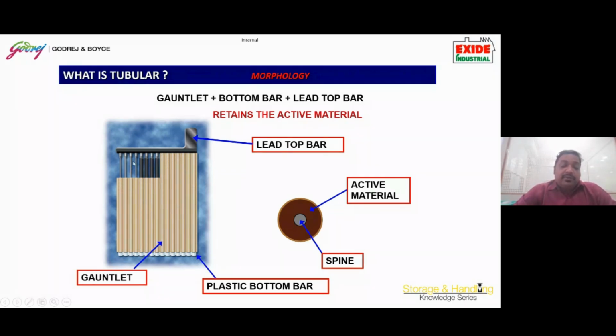Over a period of 2 to 3 years, the battery starts losing its capacity due to shedding of the positive plate. But with every charge-discharge cycle, there is no loss of capacity for this kind of traction battery. However, towards the end of the service life, these batteries also might lose capacity as the gauntlet loses its strength and shedding starts happening. So when we talk about cyclic applications, these tubular plates are the best designed and suited because they will not shed.